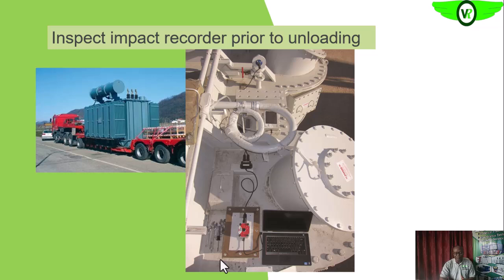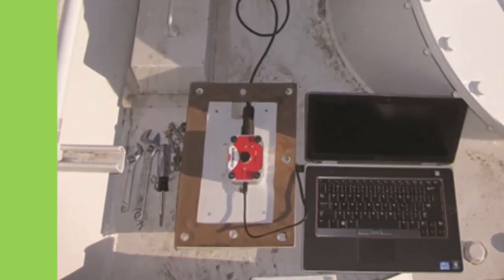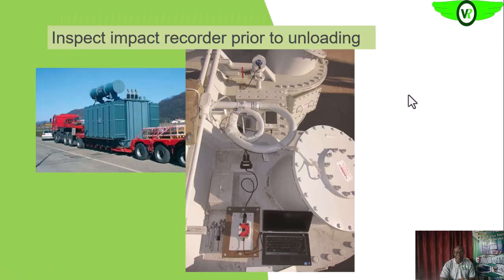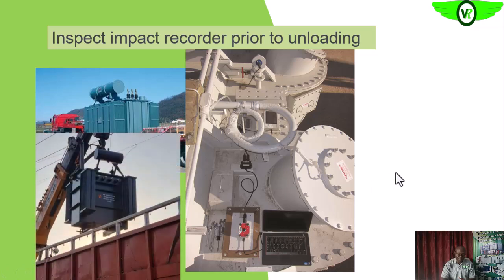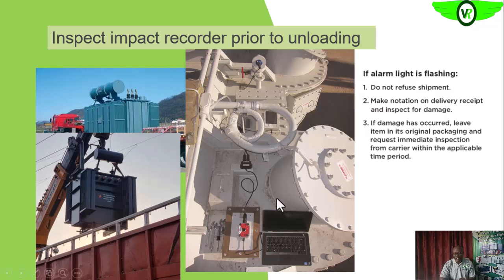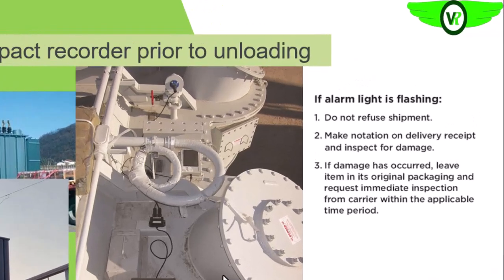If it's a new transformer that is newly brought to our facility, we want to look at the impact recorder. We can do that before it is unloaded, while it is still on the flat bed. Okay, so this is the impact recorder. We download the information from the impact recorder before we drop the transformer. This is to ascertain the degree of impact during shipping and transportation. If we see that the light here is flashing, it's not enough for us to refuse the shipment. We need to analyze the information to ascertain the degree of impact.